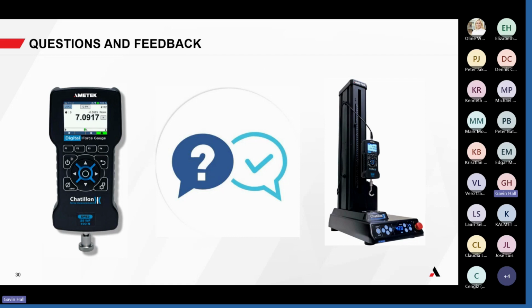This makes it a little bit more ideal for PLC environments where you want an external computer control or overriding control to use the gauge as a piece part within a test procedure. So yes, there is an ASCII command set that can be sent to put the gauge in a certain mode, to change units, to retrieve particular data, and to start and stop the test.